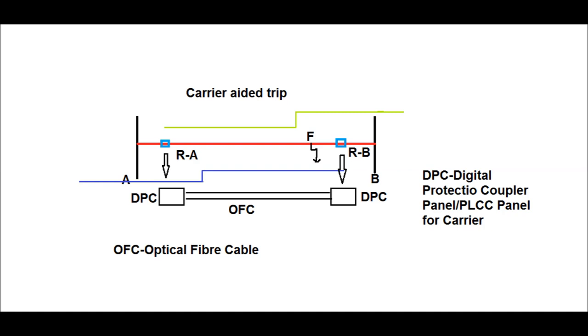But relay B senses the fault in zone 1 time. It will send a signal to the carrier protection channel, or digital protection coupler panel. The digital protection coupler will convert the analog signal to a digital signal and send it through the optical fiber cable connected via the transmission line ground wire to the far end of the substation. The same signal is received by the digital protection coupler panel at the A end side, and it converts it back to an analog signal.